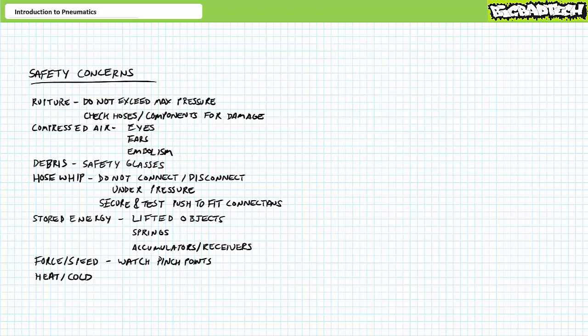The compressor may be turned off, but lifted or suspended objects and components like receivers, springs and accumulators may still pressurize the system. Finally, fluid under pressure and moving through a system can sometimes present thermal danger. Compressors in pneumatic systems can be unusually hot due to the compression process and equally as cold when discharged. Allow time for these components to return to ambient temperature between shutdown and maintenance.